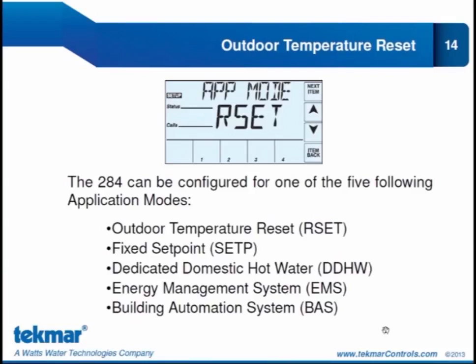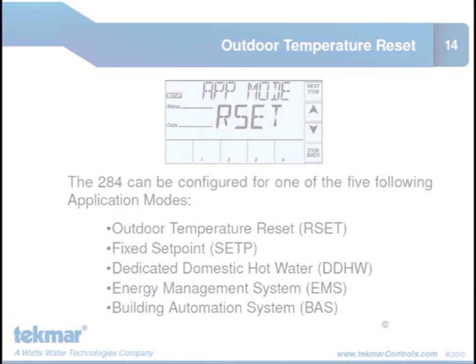Now, how do these different application modes differ? Well, one of the ways they differ is on the number of water temperatures that they allow. If we're in outdoor temperature reset mode, we can have a space heating water temperature plus a domestic hot water temperature and a set point temperature. So this application mode accommodates 3 different water temperatures. If we're in the energy management system application mode, the input we receive will be for space heating, and we can also accommodate domestic hot water set point call and a set point call. So 2 additional calls can be connected to the 284 for 2 additional water temperatures.